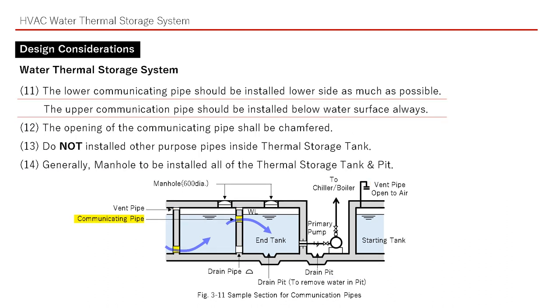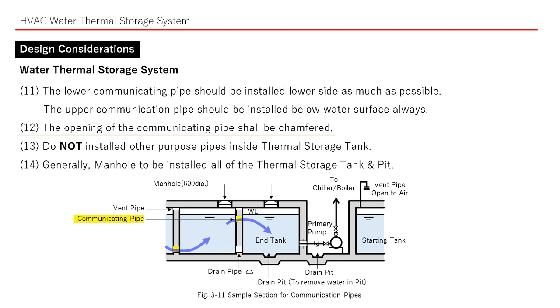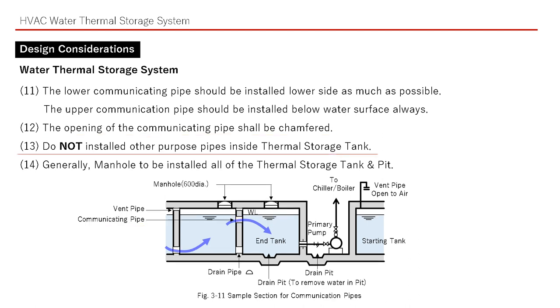The lower communicating pipe should be installed on the lower side as much as possible. The upper communicating pipe should always be installed below the water surface. The opening of the communicating pipe shall be chamfered to make a smooth flow. Do not install other purpose pipes inside the thermal storage tank.